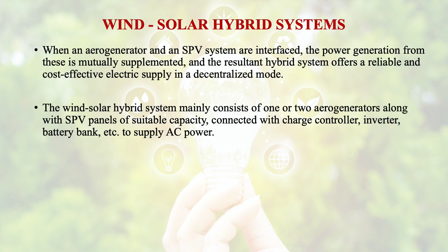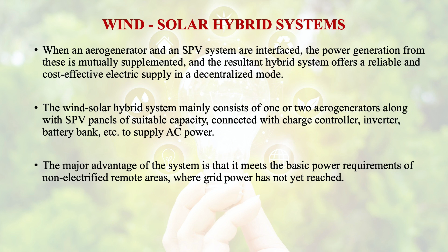Then comes the wind-solar hybrid systems. When an aerogenerator and a solar photovoltaic system are interfaced, the power generation from these is mutually supplemented, and hence they are called a hybrid system. These kinds of systems are more reliable and more cost effective in terms of electric supply in a decentralized mode. The wind-solar hybrid system mainly consists of 1 or 2 aerogenerators along with solar photovoltaic panels of suitable capacity, which are connected with a charge controller, inverter, battery bank, etc. to supply AC power. The major advantage of this system is that it meets the basic power requirements of non-electrified remote areas where grid power has not reached yet.